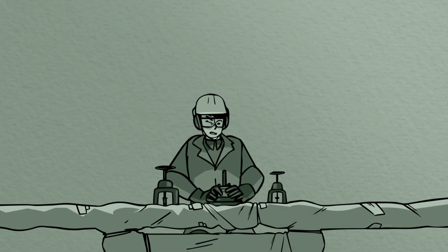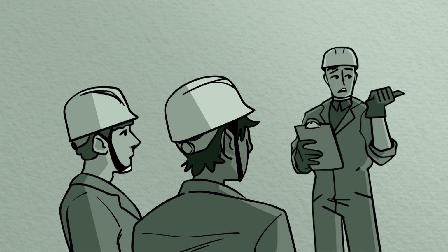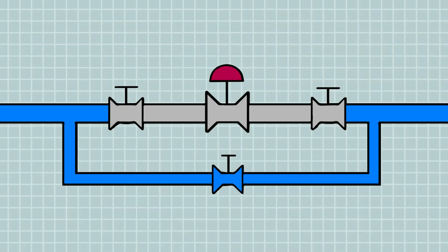This type of burn injury is typical of the many reported to the UK P&I Club every year. The crew thought the pipeline had been properly drained, but pressurized steam and hot water remained in the system, either because the procedure for doing so was not correctly followed, or because the section of pipeline being worked was not properly isolated from other parts of the steam system.